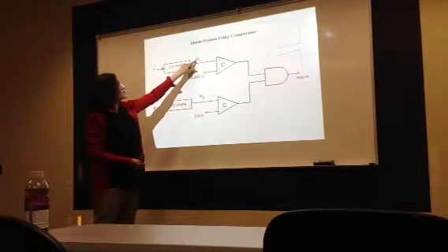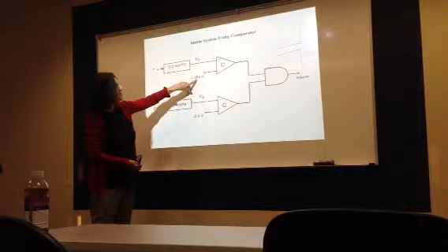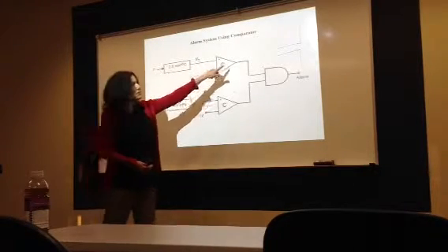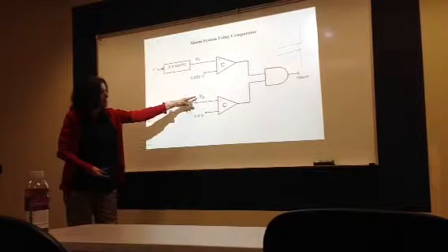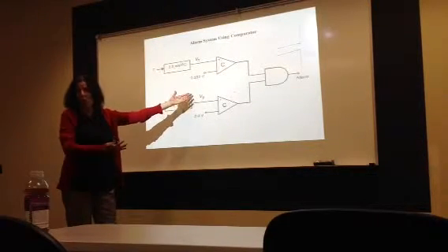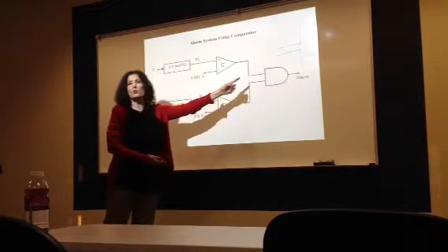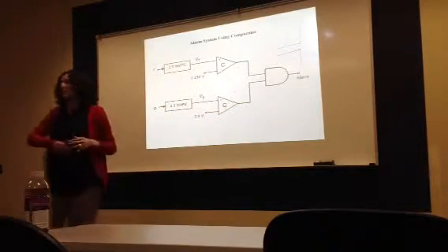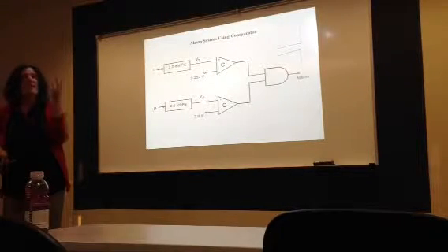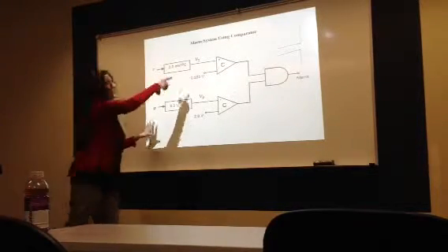Temperature voltage, right? If the temperature is greater than this, the output is true. And here we have the pressure. If it's greater than 2 as a voltage signal, that will be true. So the alarm should show when both of them are bad, both of them above the limit. If I put or, either one will get me to trigger the alarm. We had some of that.